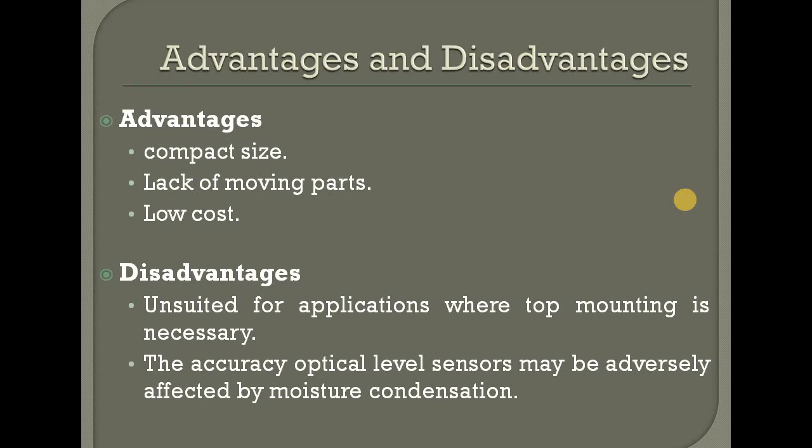The optical level sensor has advantages: compact size, lack of moving parts, and low cost. Disadvantages are that it is unsuited for applications where top mounting is necessary. The accuracy of optical level sensors may be adversely affected by moisture condensation. Additionally, it does not perform well if the sensor body is not clean. These are sensors with high and low cost considerations, and there is an additional disadvantage regarding conductors.